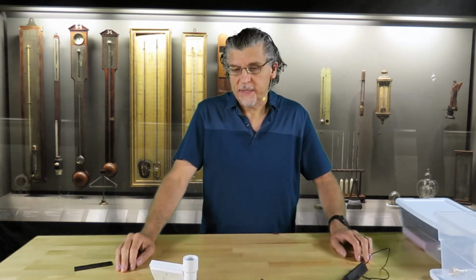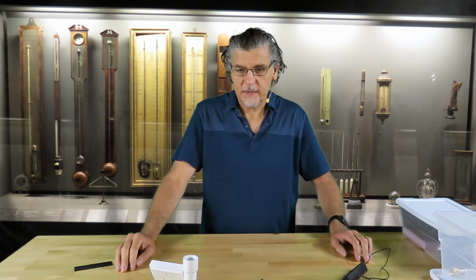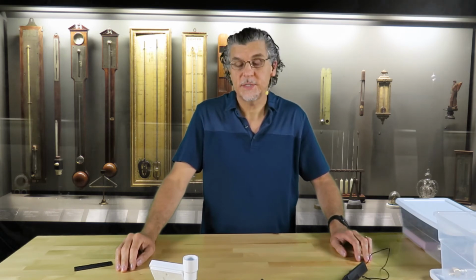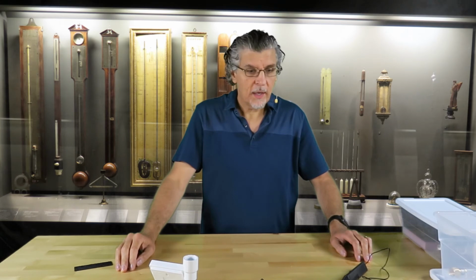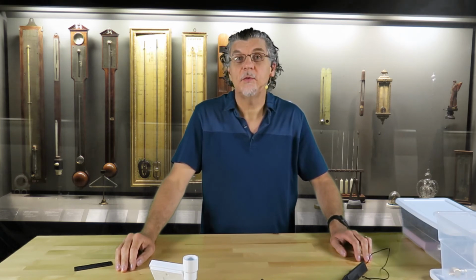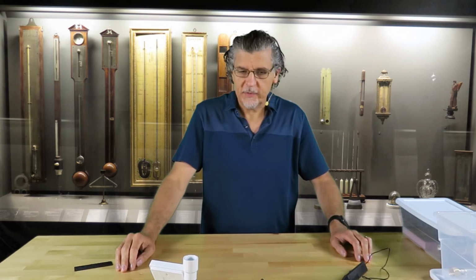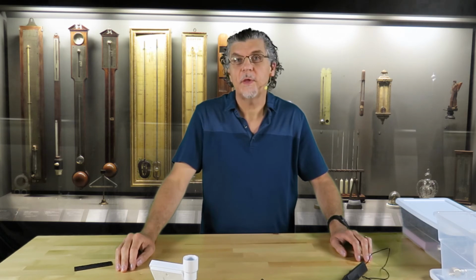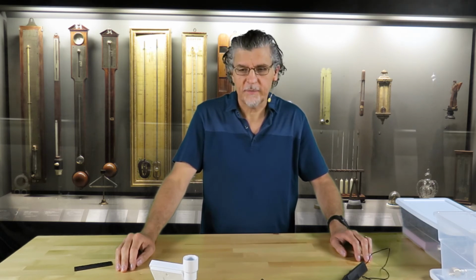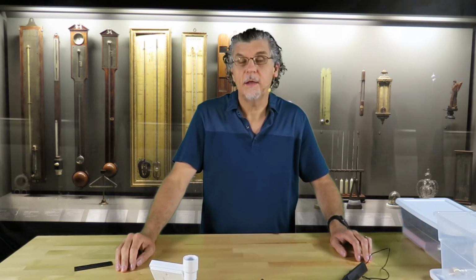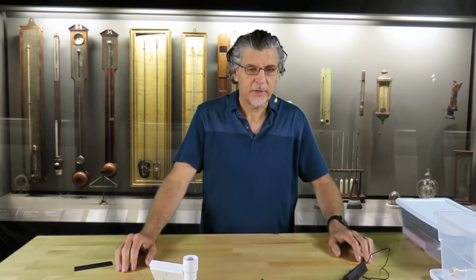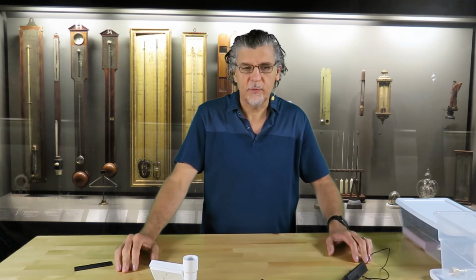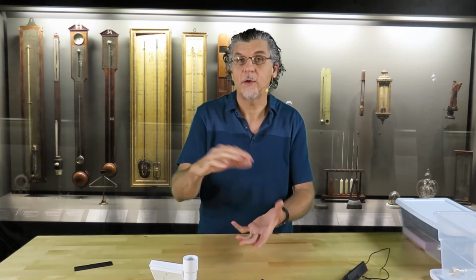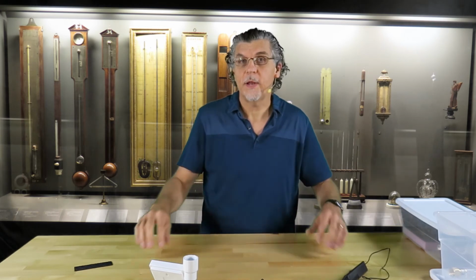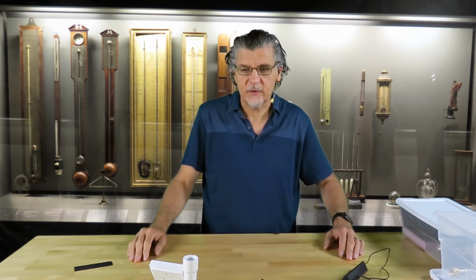So now that we've completed the build part of the experimental apparatus to perform the calibration with our 5 temperature sensors, we're now at a point where we can take this to the kitchen. And what I'll be doing is putting it onto a table, and we'll perform 2 separate calibration experiments. The first one will involve taking water and placing it into a kettle and bringing it to a boil, and we'll use about 2/3 of the kettle filled with boiling water, and then we'll add cold water to that, and the net result is we'll have water at a temperature between 60 and 70 degrees C.